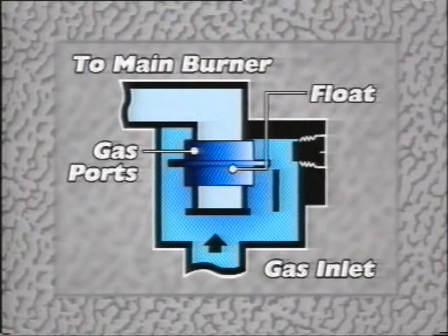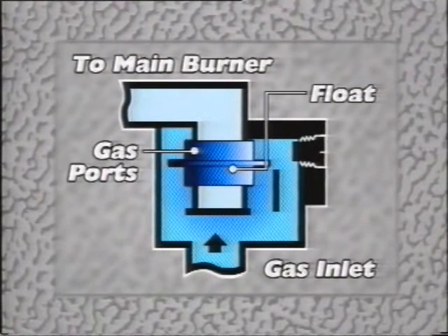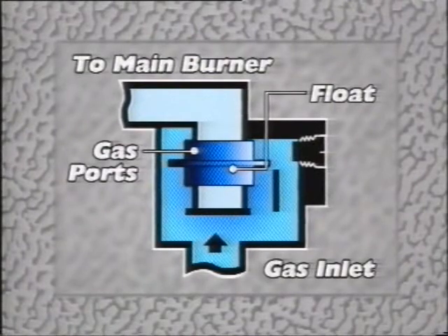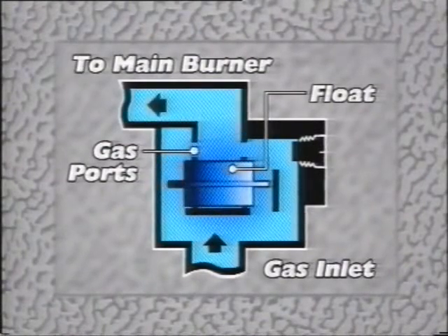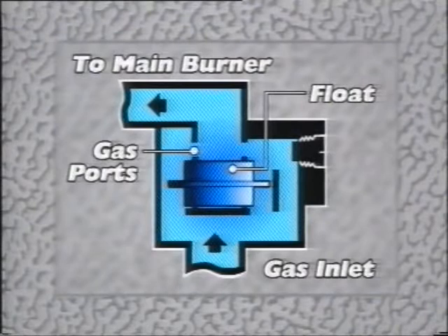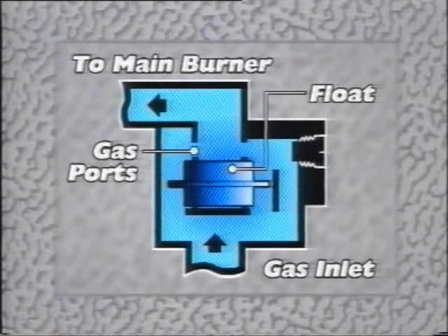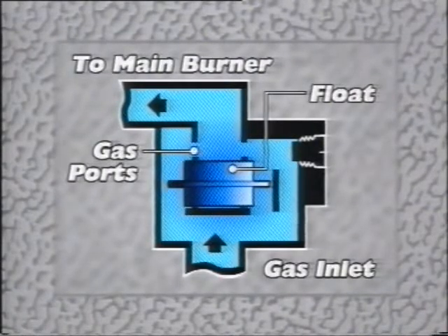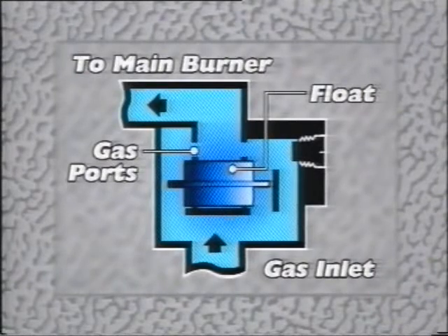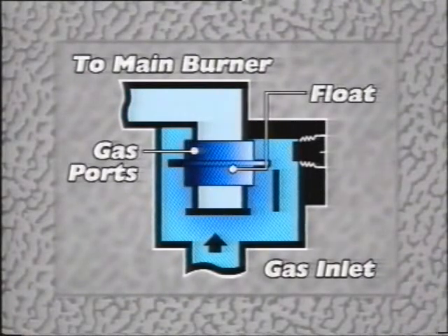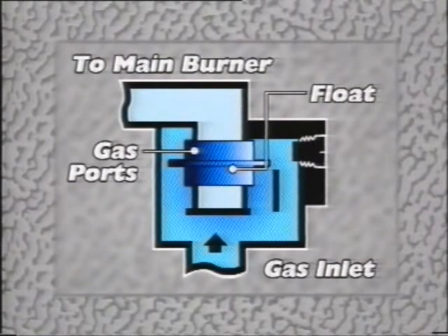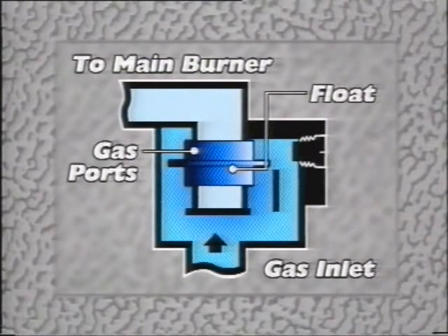Basically, the governor's an aluminium disc float which slides over a vertical tube. The various gas ports in the tube are closed or opened depending on where the float is. As the supply pressure increases, so does the flow, and consequently the pressure differential across the float. That makes the float rise, closing ports as it moves, and so reducing the flow again.